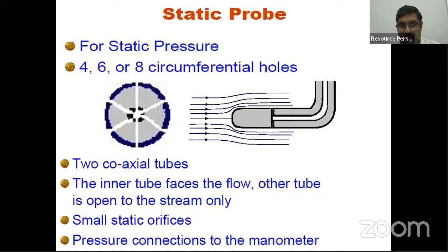And then for the measurement of dynamic pressure, you combine both the static and the pitot probe. That will give you the dynamic probe. So you see here the stagnation pressure is measured at the center, and the static pressure is measured at the circumference. The difference between these two will give your dynamic pressure, which is your velocity pressure. Okay. So here there is an issue. Maybe if you see in this figure, this static hole, this hole is close to the nose.